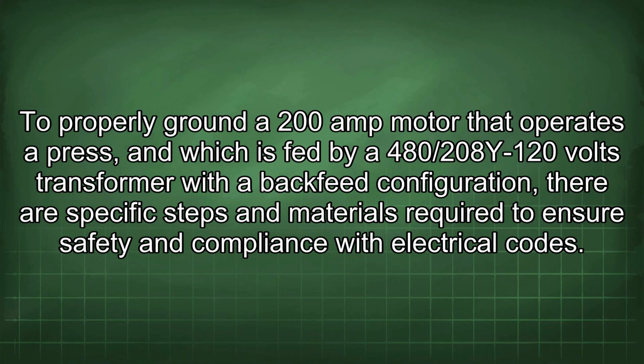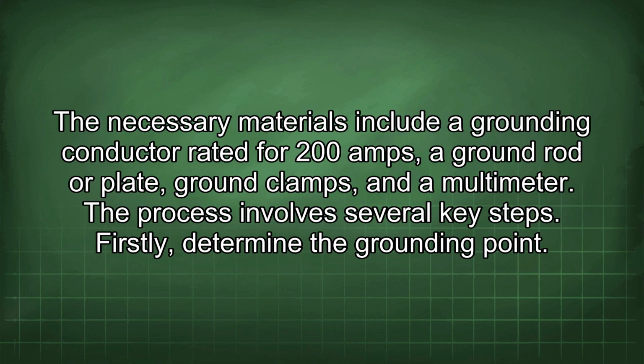To properly ground a 200-amp motor that operates a press, and which is fed by a 480/208Y-120 volts transformer with a backfeed configuration, there are specific steps and materials required to ensure safety and compliance with electrical codes. The necessary materials include a grounding conductor rated for 200 amps, a ground rod or plate, ground clamps, and a multimeter. The process involves several key steps.